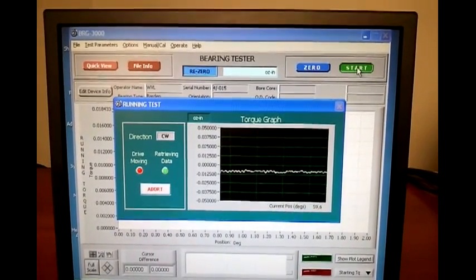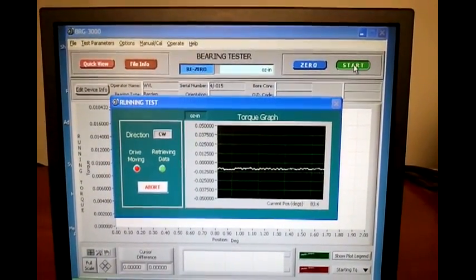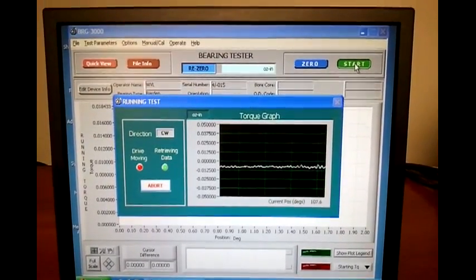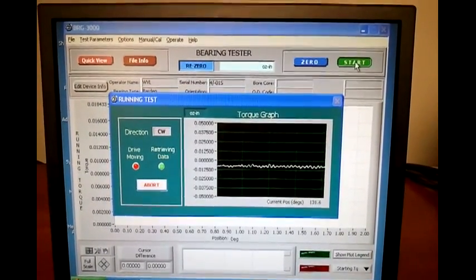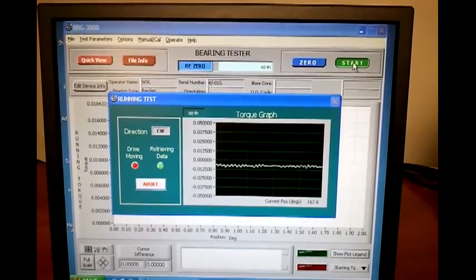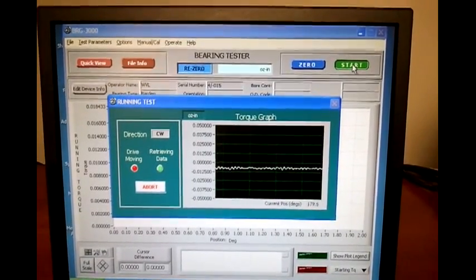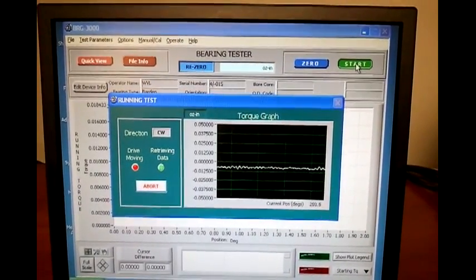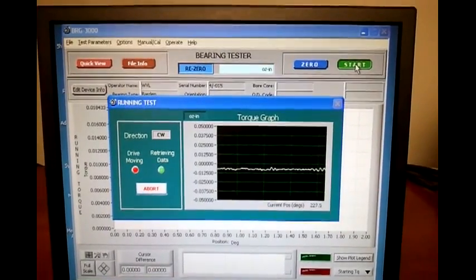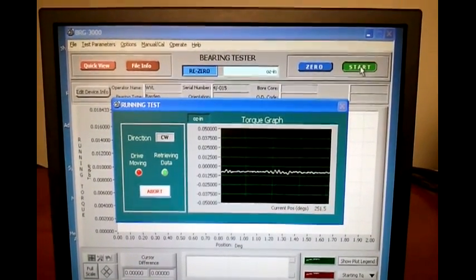Now it is going to drive 360 degrees in one direction, turn around, and drive 360 degrees in the opposite direction. At the end of the test, it displays the torque value measured in both directions.